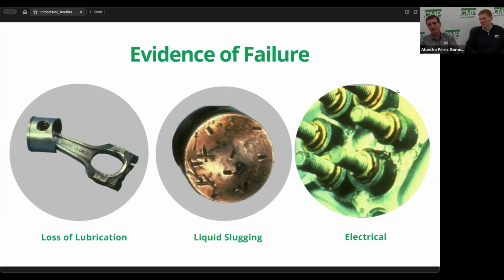We really hadn't touched on part wind start. If you do commercial refrigeration or air conditioning long enough, you'll run up on something that has two contactors that bring the compressor on. If you're changing out that compressor, you need to mark your terminals or your contactors. If you change them, mark every wire exactly and put every wire back on exactly. One contactor runs half of the motor and the other contactor runs the other half, and they'll either bring them in together or a split second behind one another. But if you just cross one wire, you have half the motor trying to turn clockwise and the other half trying to turn counterclockwise. So it just hums and locks up, and it doesn't take but maybe 15 or 20 seconds to burn the compressor right up because you're pulling locked rotor amps on the little motor wires. That's part wind start, and eventually, if you do it long enough, you will come up on those systems.